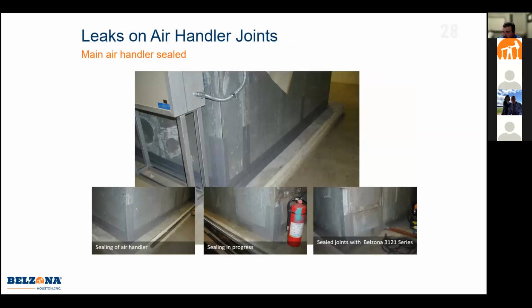So the final topic is something everybody deals with as well: leaking joints on your air handler, whether sealing edges or bases, since these air handlers generally move, shake, and vibrate a lot, especially during service. This is that Belzona elastomeric series that takes really low prep. You don't have to blast it, you don't really have to grind it either. You can come in with some sandpaper, a wire brush, degrease the area well, and put your reinforced system over these seams, and that'll stop your leaks. Again, given the area these air handlers sit in, it's very hard to pull out full panels or even shut them down to replace them, which can take days. With this method, you don't even have to shut down — we can come in and do it while the machine's still running.